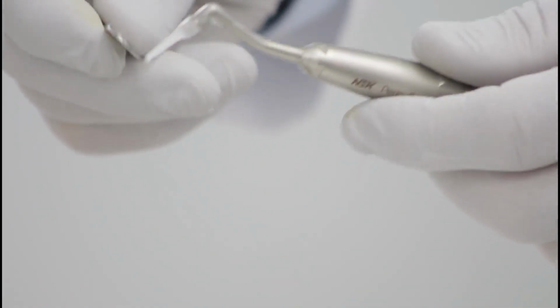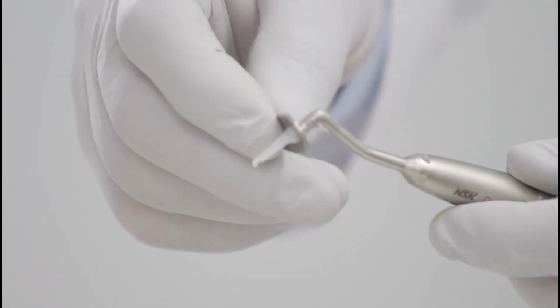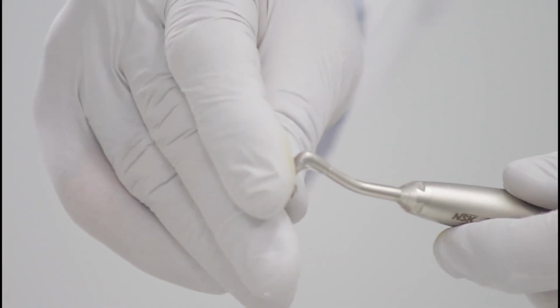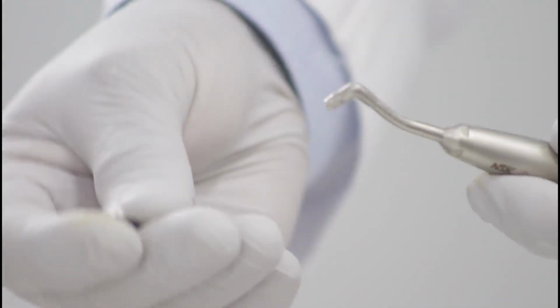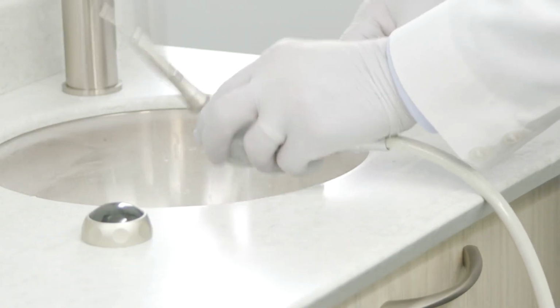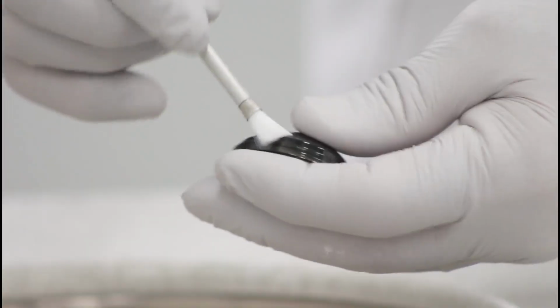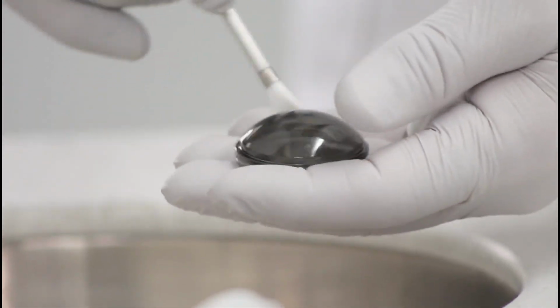Sterilization. Autoclave sterilization is recommended. Remove the nozzle tip. Dispose the remaining powder in the case. Disassemble and clean Perio-Mate thoroughly as instructed before.